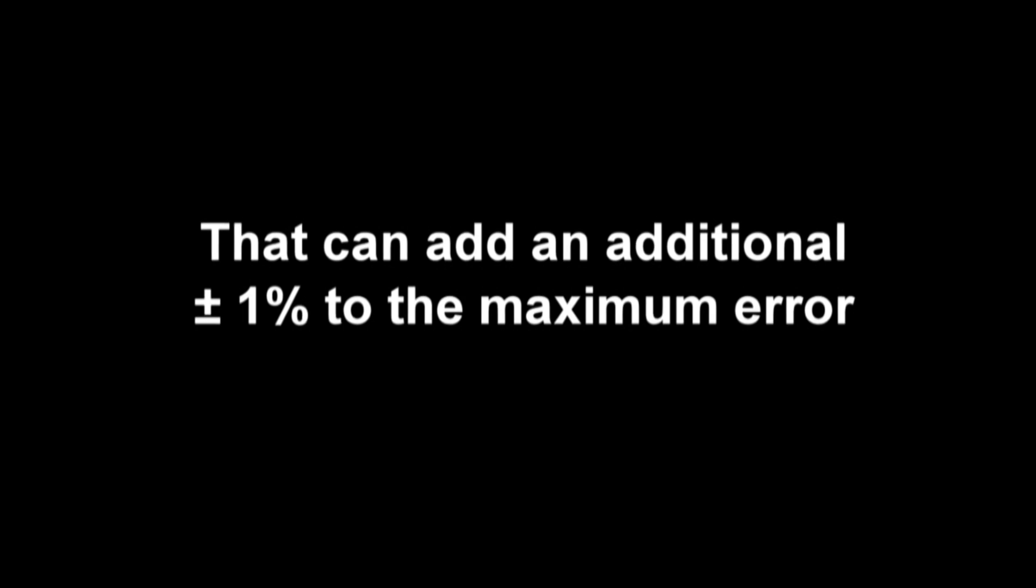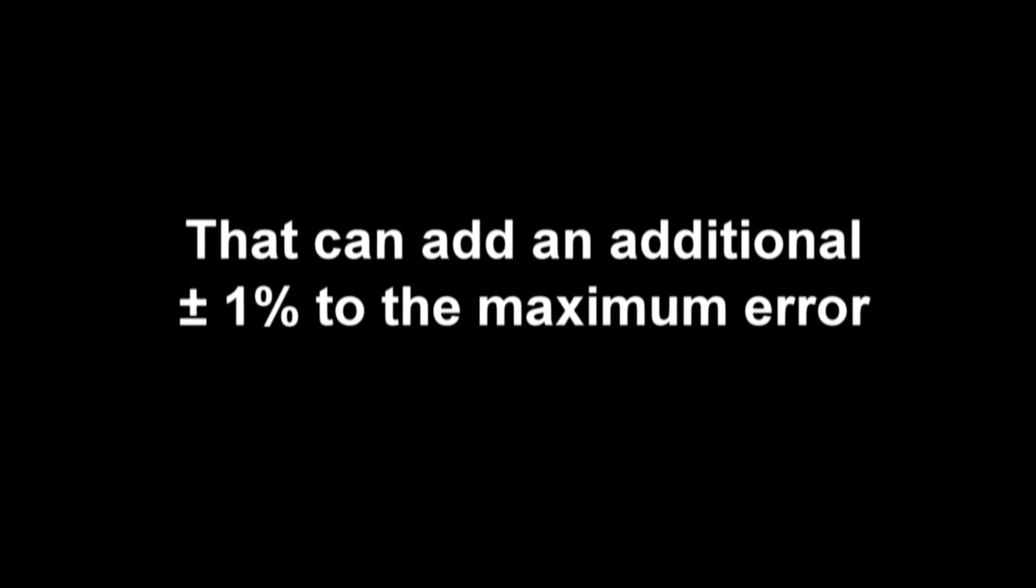Everything I've said until now is for the conditions calibrated. In addition to this, if measurement is at a different power value than we calibrated it, there can be an additional error in reading due to non-linearity. That can add as much as plus or minus 1% to the maximum error. That error is usually the most near the highest measurable power and when the sensor gets hot.